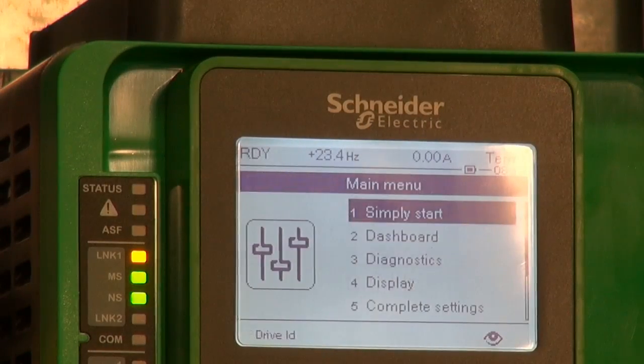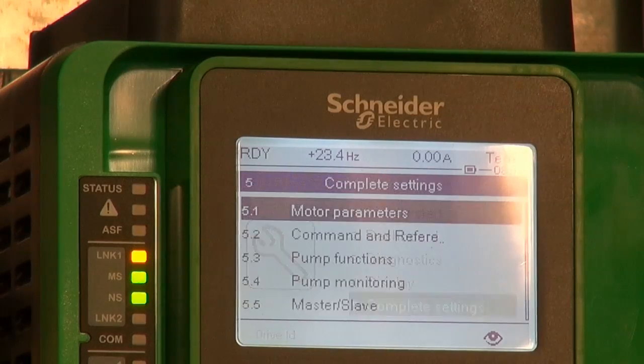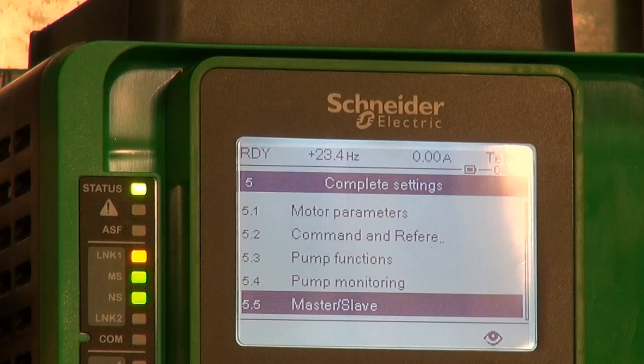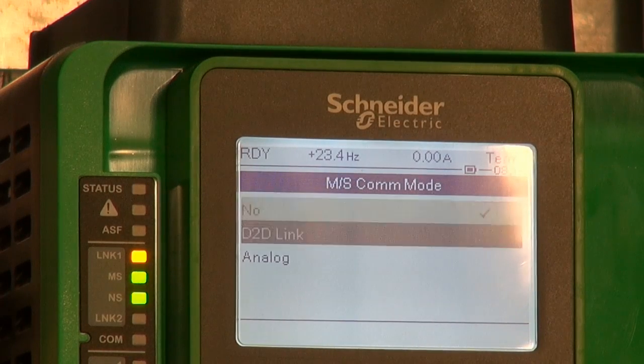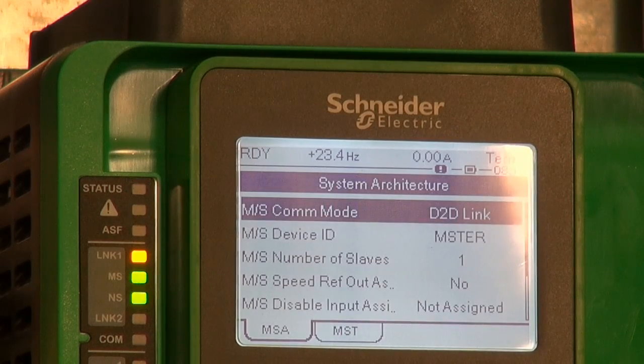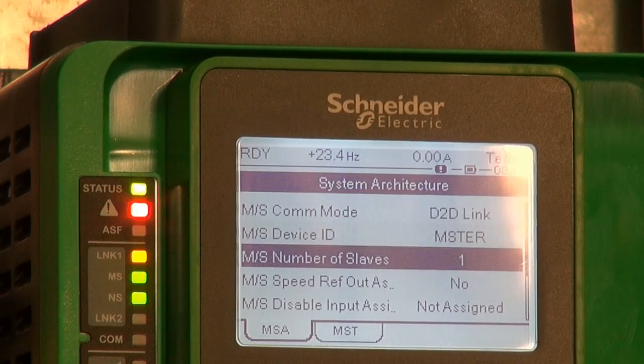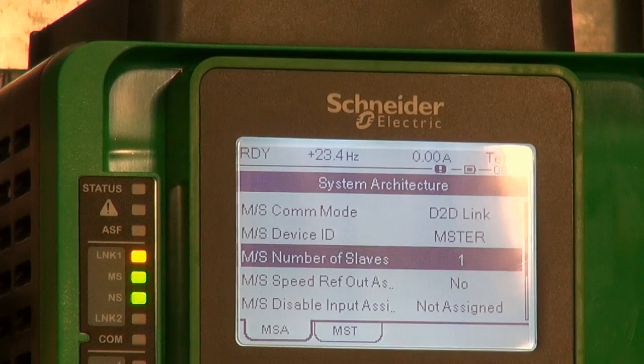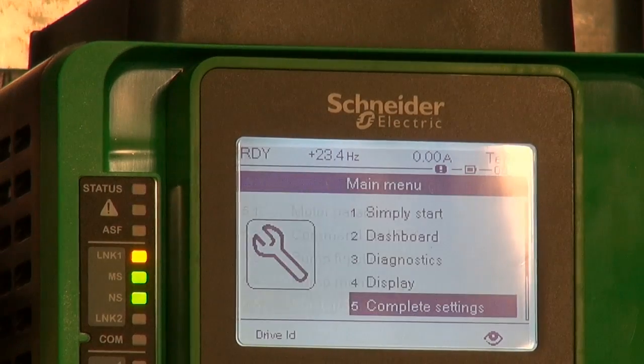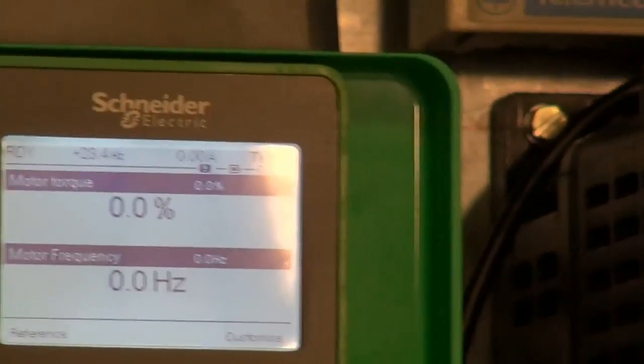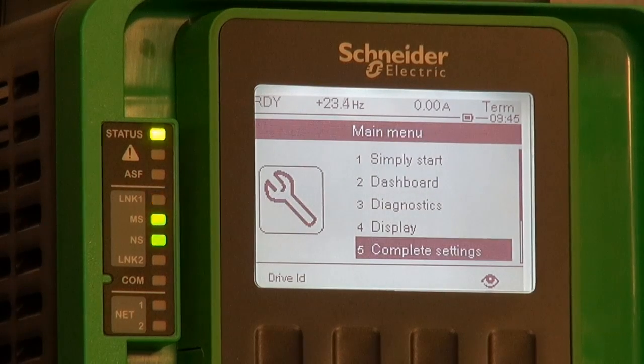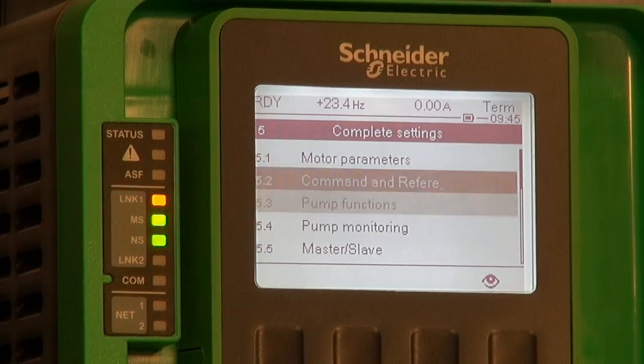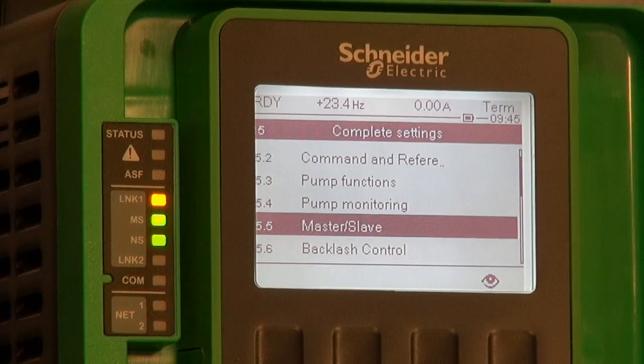The Altivar Process allows choosing the master-slave function on speed or torque management. For the settings: on the master, we activate the function, choose master or slave, and set the number of slaves. On the slave, we activate the function, select the slave number, and the application is ready to run after a power cycle.